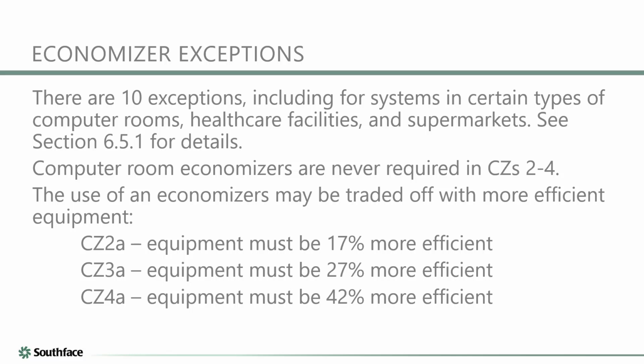So I also see listed here some exceptions for places that might not want high outside air volumes or might have limitations around humidity control. So that's another thing to be considered here. I see computer rooms, healthcare facilities, supermarkets. I mean, these are places that have their unique reasons for why they wouldn't want a large volume of outside air to be dumped into the building.